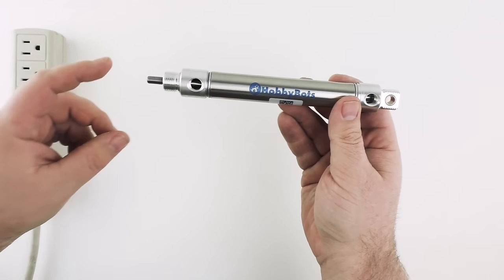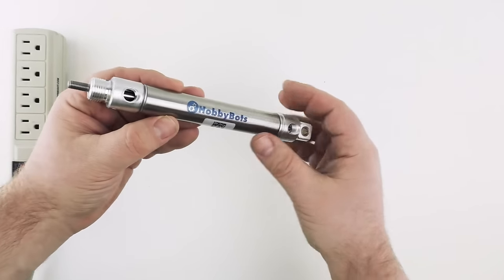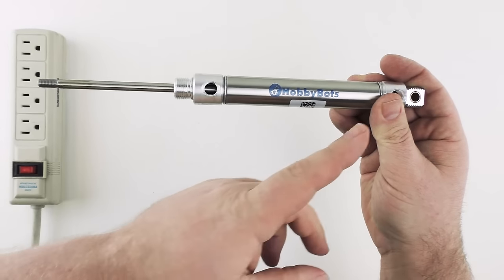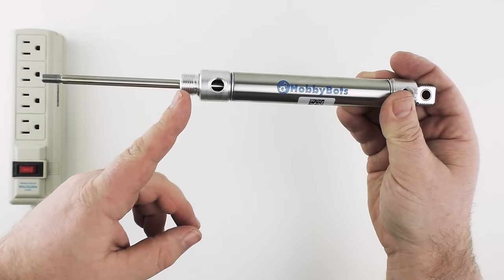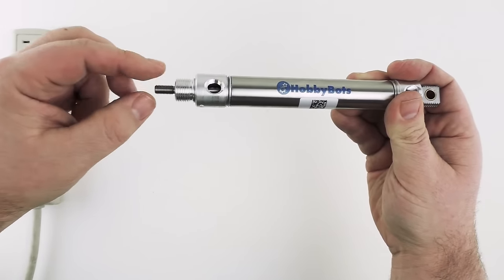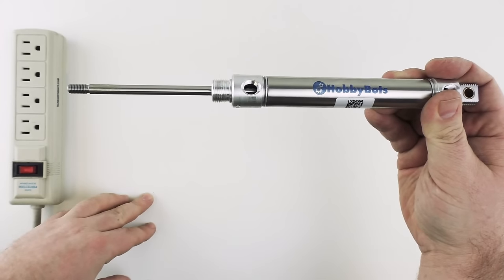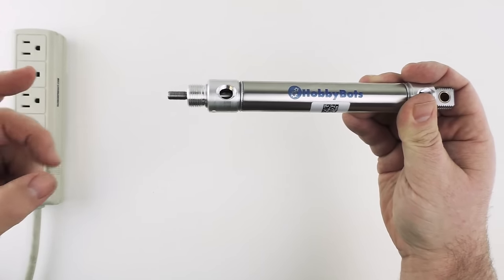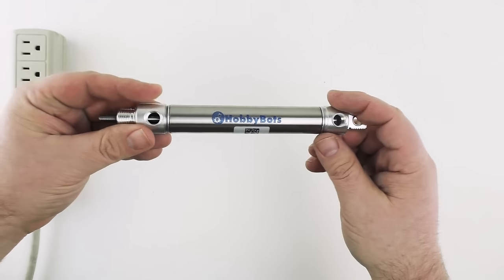The two most common things you're going to hear are stroke and bore. We'll start with stroke. Stroke is the distance that the cylinder rod extends when air is applied. You can see here that this cylinder has a stroke of three inches. That means that when air is applied this rod is going to extend three inches. The longer the stroke the longer this will extend and the longer the overall body of the cylinder will be.